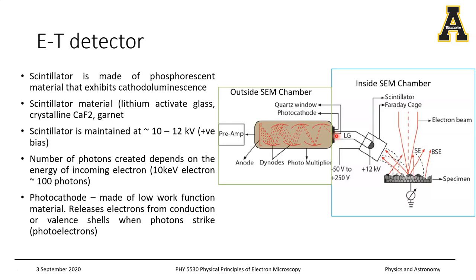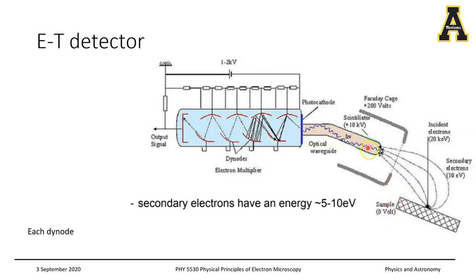To recap the signal path: electrons from the incoming beam generate secondary electrons, which are attracted by the Faraday cage, then accelerated toward the scintillator by the higher voltage. The scintillator generates photons, which travel through a light guide to the photocathode. At the photocathode, the photons are converted back into photoelectrons. The schematic shows secondary electrons flowing in, the photon (h-nu) traveling to the photocathode, generating new photoelectrons that then enter the photomultiplier tube outside the chamber.